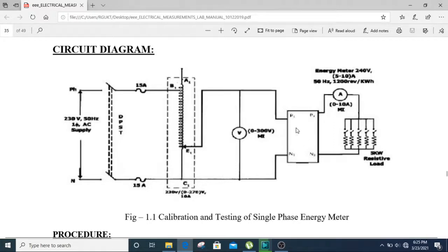Here it is the energy meter, which has a meter constant of 3200 revolutions per kilowatt hour. Meter constant K is equal to number of revolutions per kilowatt hour. From that we can get the energy measured by this energy meter. Energy consumption in kilowatt hour will be equal to number of revolutions divided by meter constant. Here we are considering 10 revolutions. So the energy measured by this energy meter will be equal to 10 revolutions divided by 3200 revolutions per kilowatt hour. That is the energy measured by this energy meter. This is the instrument which is under test.